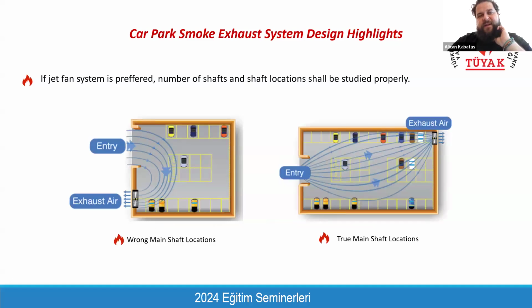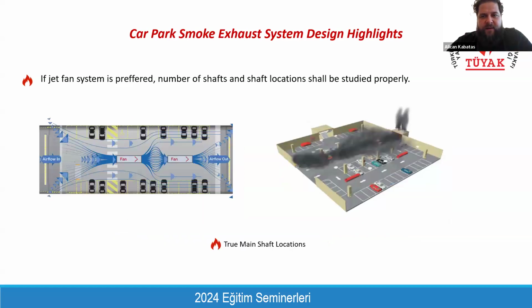But what is the negative side of the jet fan system? It requires exhaust shafts and it requires makeup air, fresh air inlets. That's why you need to discuss with the jet fan designer to understand how many shafts are required. And these shafts should be located in such a manner that we can route the smoke from the makeup point to the exhaust point without having a bypass. If you locate these shafts just next to each other, instead of extracting smoke from this part of the car park level, you just bypass the fresh air and the system won't work. That's why the shaft locations and the number of shafts should be coordinated with the jet fan designer, and this coordination is also done by the architectural team.